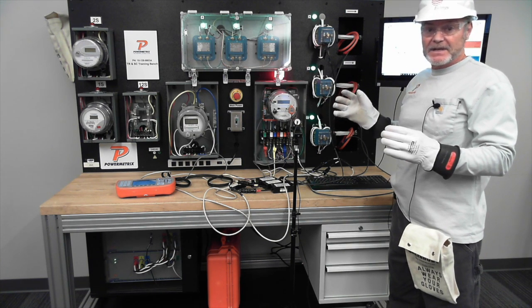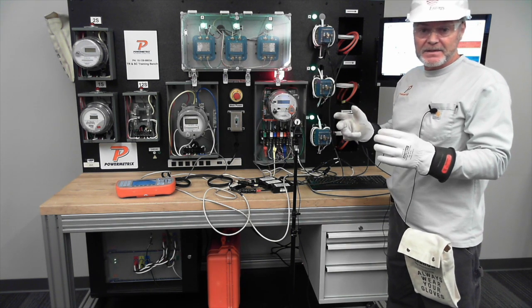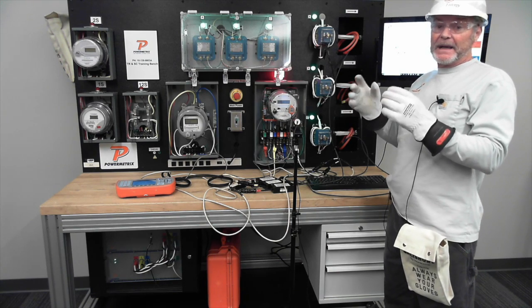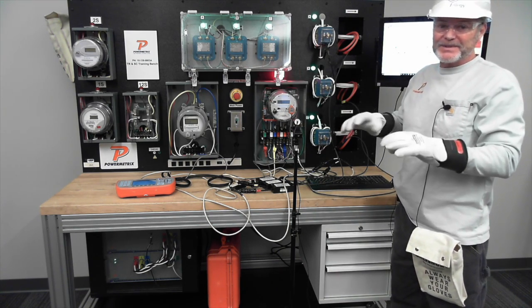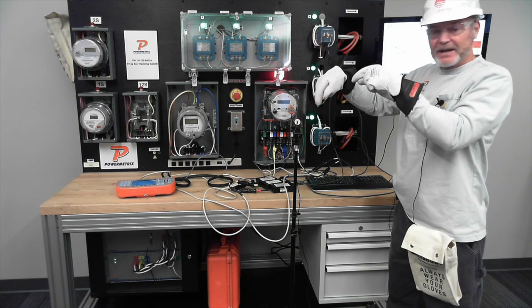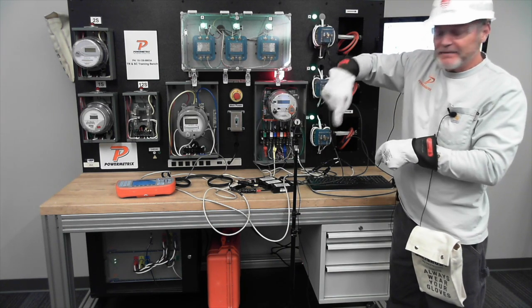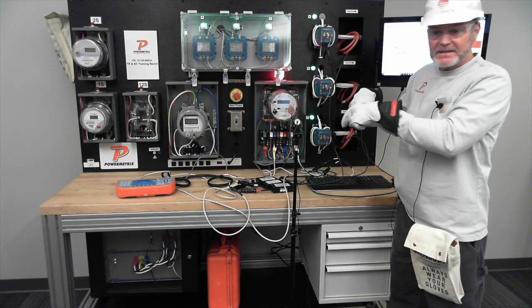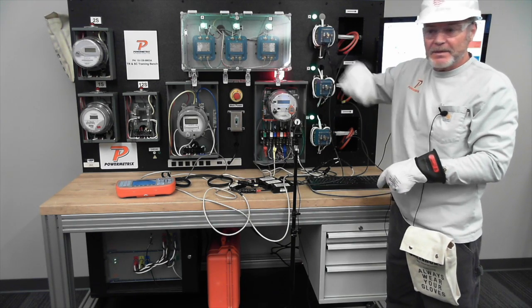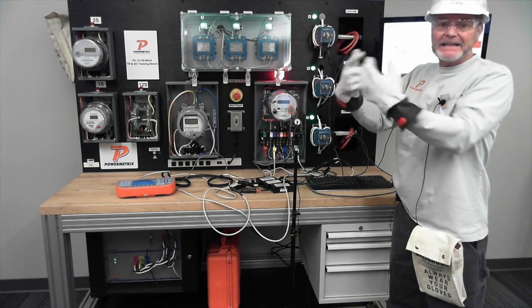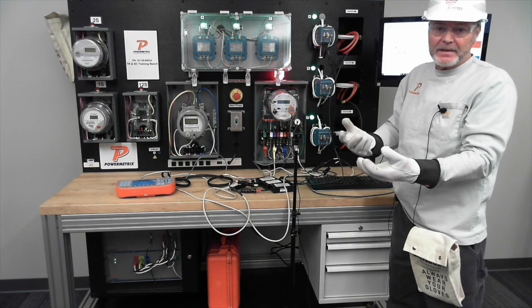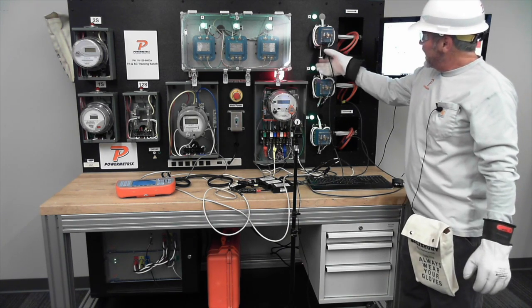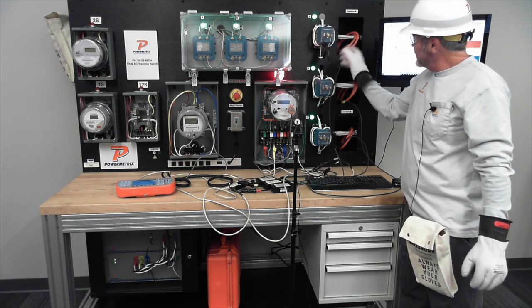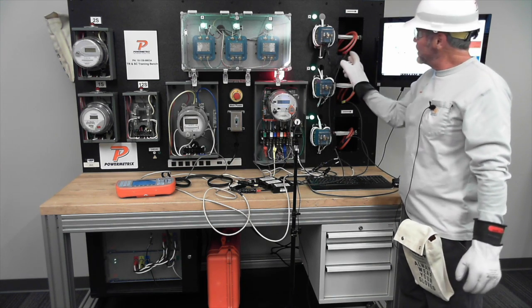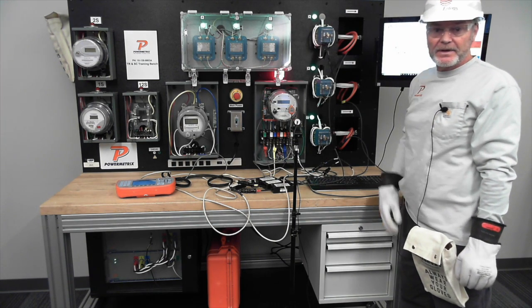So this is very similar to when you're doing a benchtop test on a CT. Okay, these people are going, man, how are you going to be able to test that thing? It's so many volts. I don't worry about the volts, right? I'm just worried about secondary current and primary current. So I can put a drive cable through that CT on top of that desk, and I can run that primary through it and measure my secondary. I'm not connected into the system, so the voltage doesn't affect me. So in the same case here, all I need is my secondary current and my primary current, and I'll do a ratio, and I'll see how close they are to 200 to 5s.